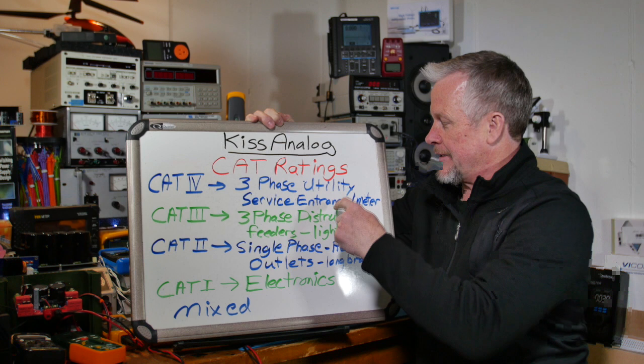And I'll tell you something else. If I am measuring current in those kinds of applications, I hope I don't get sloppy or lazy enough that I don't remember to move that probe from current. And the meter is another safety device these days, guys. A lot of the meters will say error, error, you've got to get your meter in the right spot. So if you're around dangerous stuff, category 3, category 4, or even category 2, make sure you've got the meter set in the correct position.